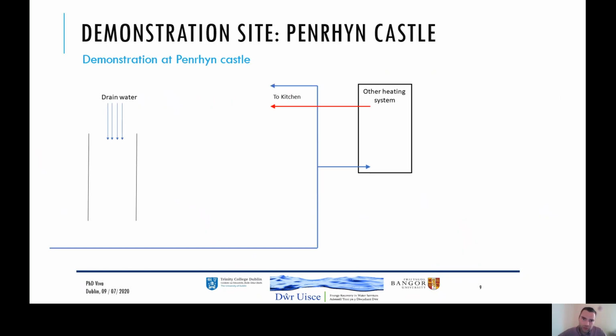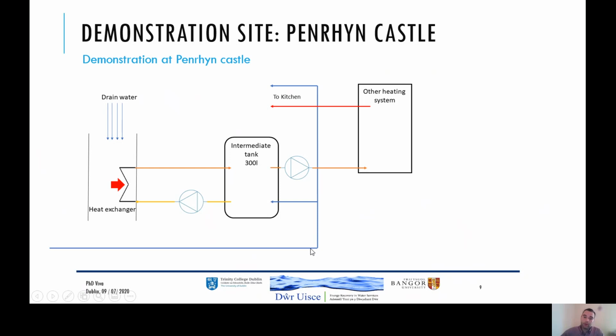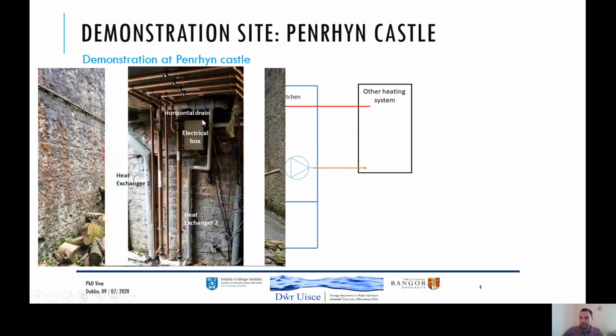Moving in then to our first demonstration site, which was the kitchen of Penrhyn Castle, a tourist attraction, where we let the fresh water into a buffer reservoir from which it was circulated and recirculated to a heat exchanger placed on the drain. When hot water is consumed in the kitchen, the water is then pumped from this buffer reservoir through the alternative heating system to the kitchen. And it's the fuel consumption of this alternative heating system that we wanted to reduce. You can see the kitchen here upstairs, the drain, our 2 heat exchangers installed, and the buffer tank here.